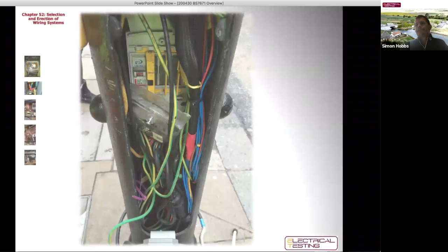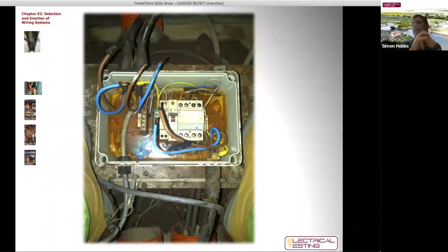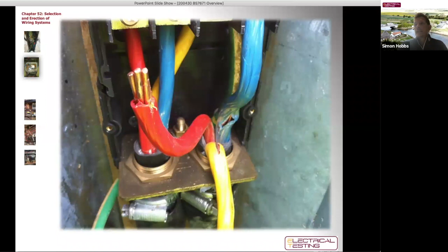So let's have a look at 52. These are the sorts of things that we're trying to avoid. This is a grouping issue. We've got too many cables in one location. They generate a lot of heat, and they could potentially be overloaded from the heat that the grouping is causing. Here we've got an inappropriate enclosure that's in a pit in the ground that's filled with water. So it's just an incorrect selection of equipment. It might be an installation issue, but certainly incorrect equipment has been chosen here. Then we need to choose the right type of cables. Initially, it might seem like that's a suitable cable for the environment, but over time, we can see here that through the cold and the heat, the insulation has split. So again, incorrectly selected cabling for the environment that it's in.